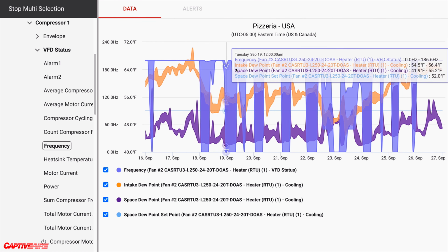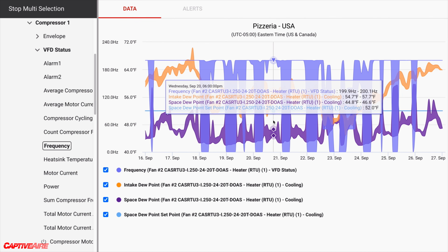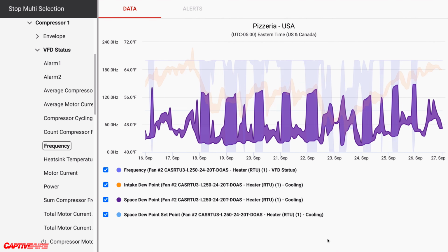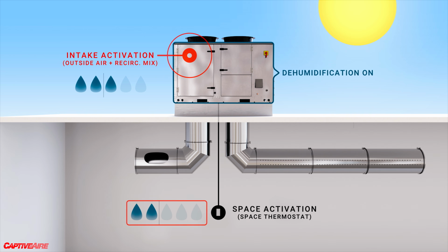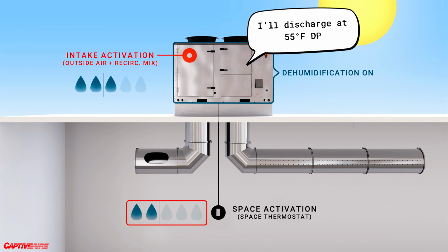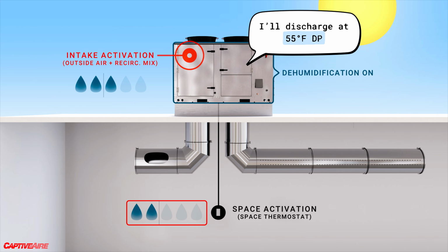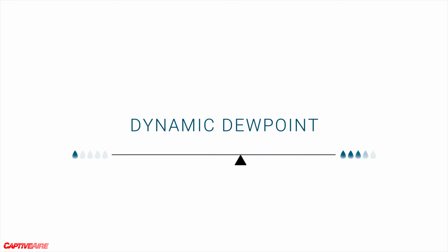So hey, if we could have been running that compressor at half speed to just dehumidify to whatever that space dew point is only, that's going to save us a lot of money. So we have a feature that does allow us to track that space dew point and then hone in our coil temps to hit exactly what the space needs to maintain that set point. This is called a dynamic dew point adjustment. Dynamic dew point gives us the ability to modulate how much we dehumidify the space, just like we're able to modulate how much we sensibly cool it.